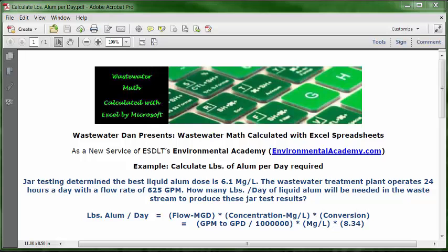This formula has three elements. One fixed element, which is the conversion factor from gallons to pounds, and the other two elements are variable based on the requirements of the problem. One element is concentration, and in this case the concentration is expressed in milligrams per liter, or parts per million. Therefore, the third element — which is the gallons of water — needs to also be expressed in increments of millions. Since this is a flowing waste stream and we need the answer in days, pounds per day, we need to express our gallons of water for a full day in increments of millions.